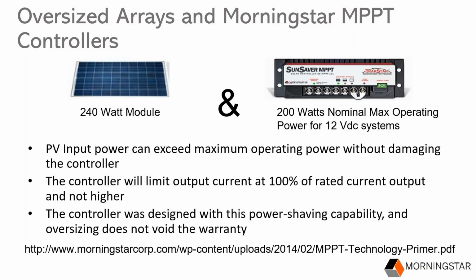I'm going to use our SunSaver MPPT as our example, but oversizing applies to all of our MPPT controller families. In this example, the SunSaver MPPT has a nominal maximum operating power of 200 watts when used with 12-volt batteries, but using a 240 watt module won't damage the controller and won't cause it to exceed its rated 15 amps of output current. You still need to adhere to all the other operating guidelines listed in the operations manual. For example, you can't exceed the open circuit voltage limits of the controller, because that would damage it.